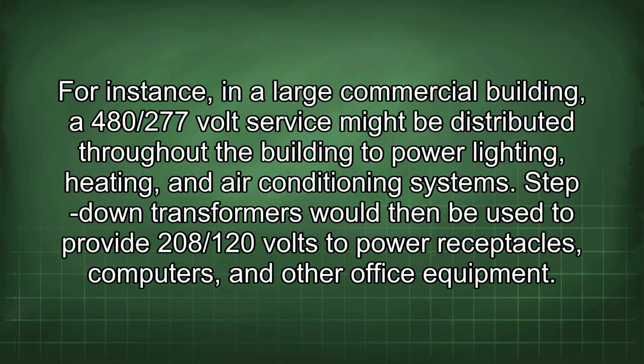For instance, in a large commercial building, a 480/277 volt service might be distributed throughout the building to power lighting, heating, and air conditioning systems. Step-down transformers would then be used to provide 208/120 volts to power receptacles, computers, and other office equipment.